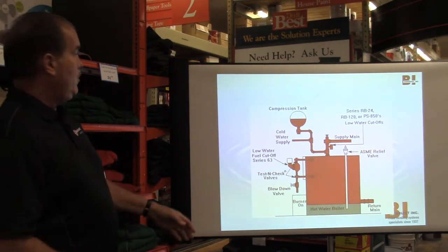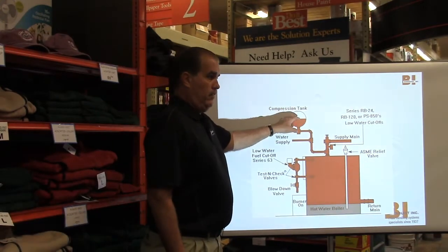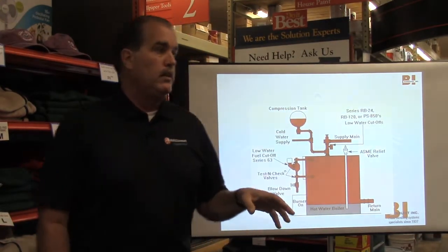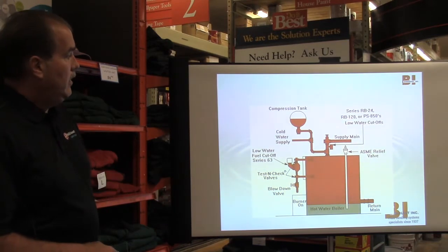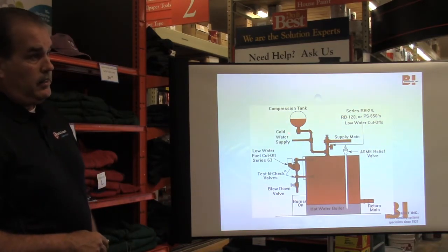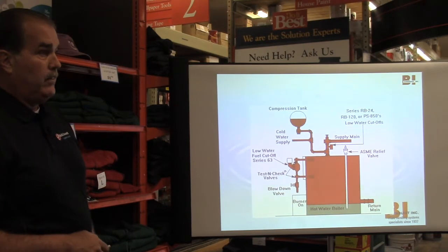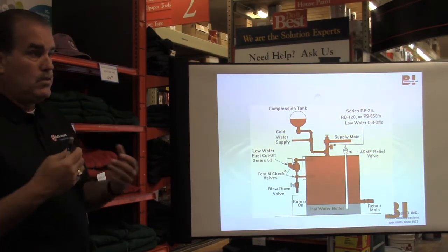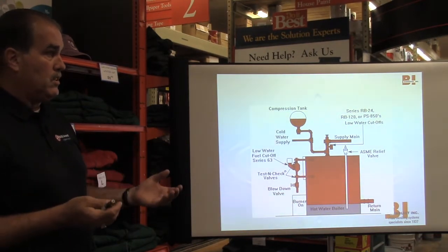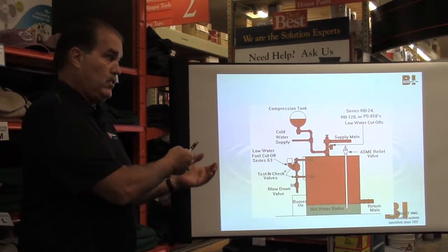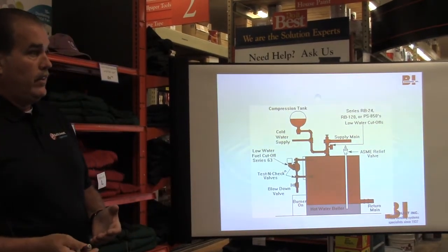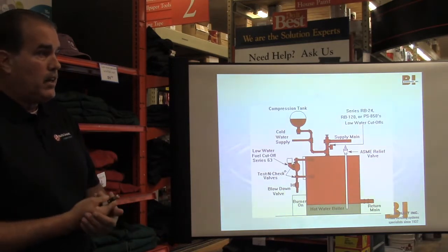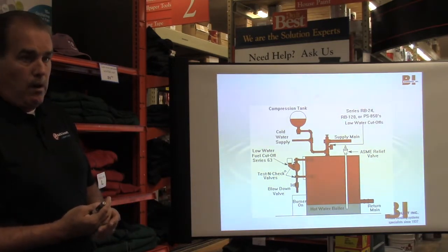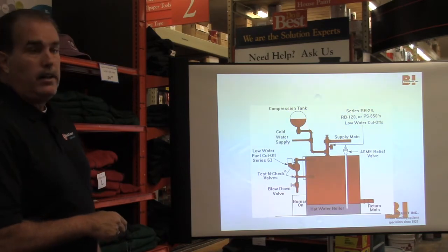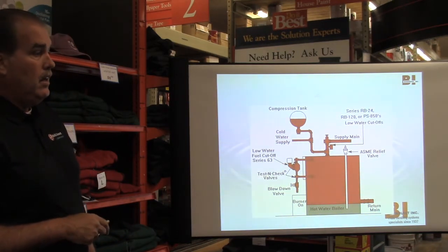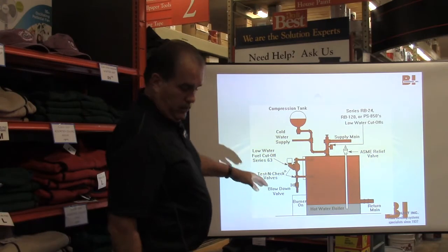And here's what's going to happen. If you waterlog your compression tank, you now have no way of knowing the tank's waterlogged. The telltale sign is that your relief valve starts popping, because the water has nowhere to go, and it's going to go through the path of least resistance, which is your safety relief valve, which is designed to take that. So that's how you know. If your relief valve pops all of a sudden and you don't know why, I would look at your compression tank.